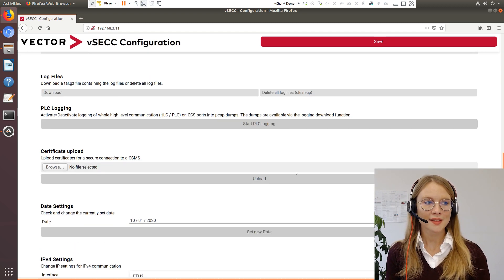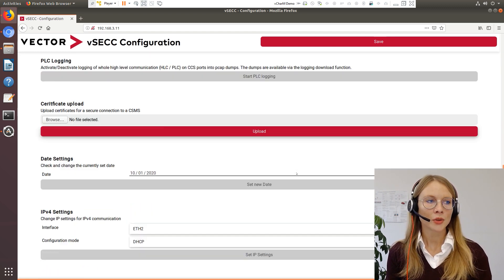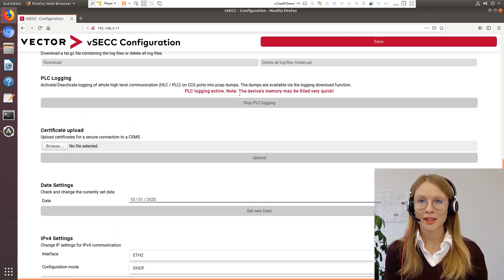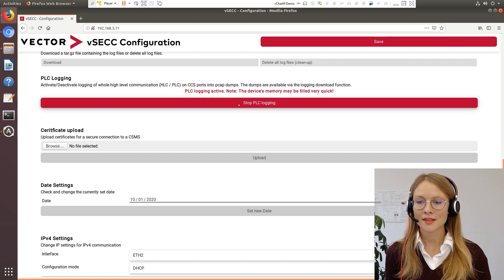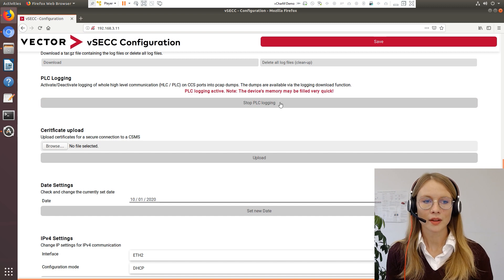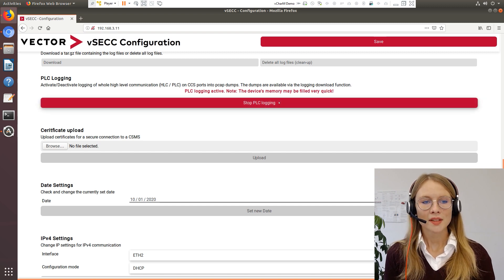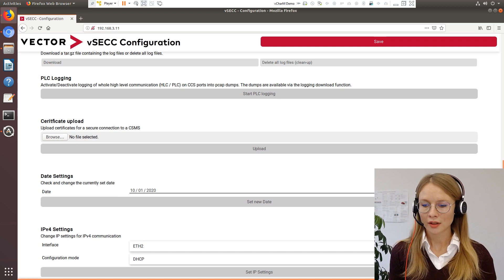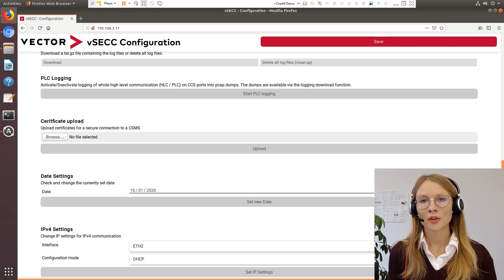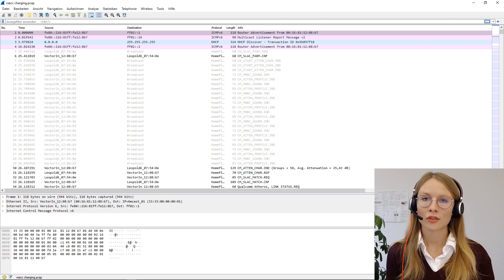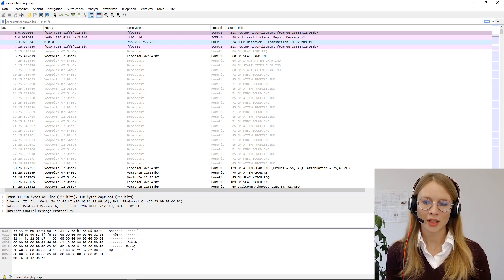Right below the log files section you can start and stop the PLC logging. You can do that directly in the web interface and the PCAP files will be stored also in the log files. When stopping the PLC communication and downloading the log files, you can open the PCAP files in tools such as CANoe or Wireshark and therefore analyze the PLC communication.